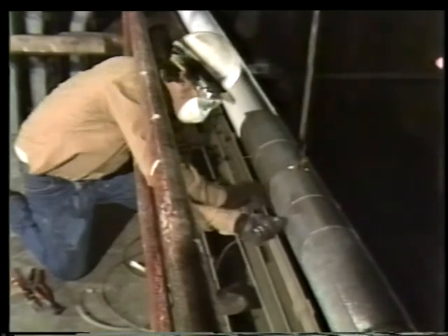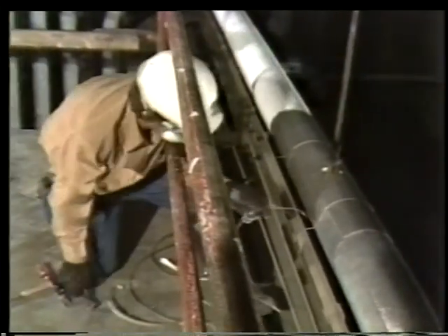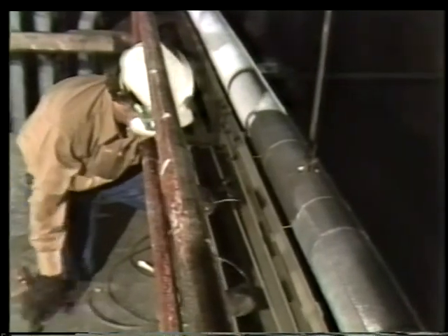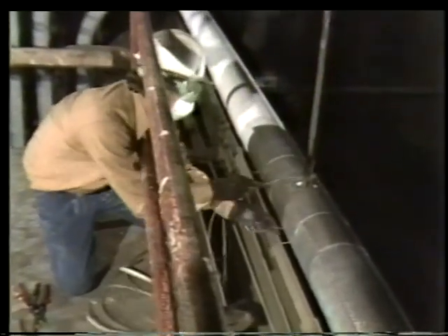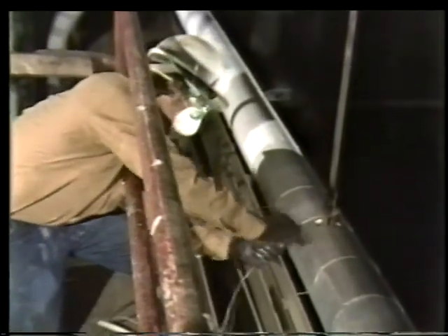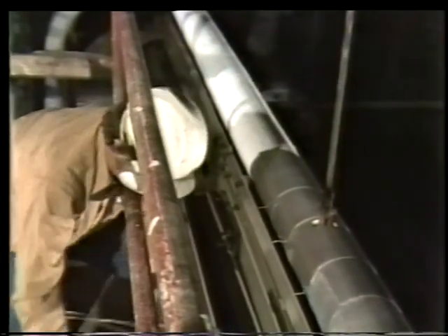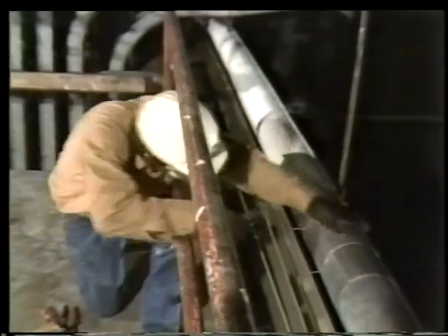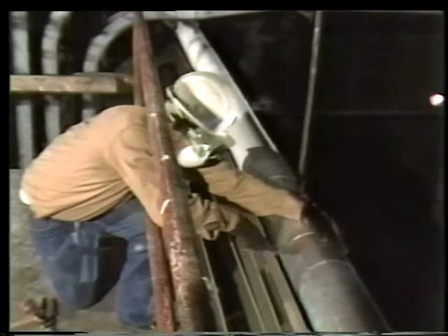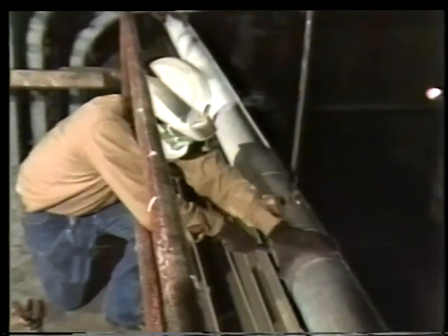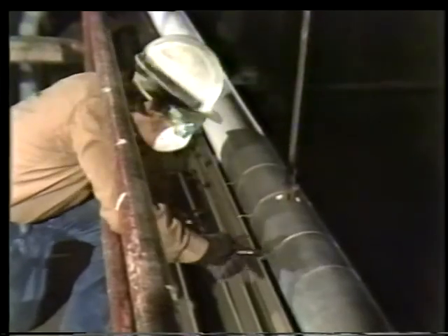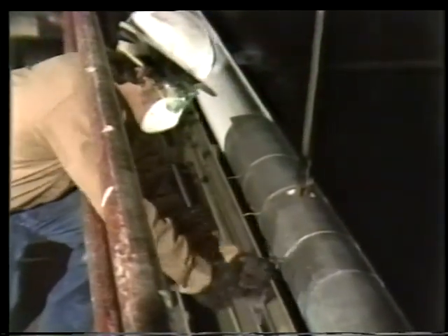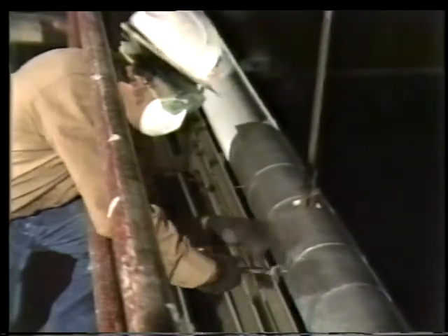Initially, the jacket is secured with wire ties. Wires are twisted on about 1 foot apart, just to hold the jacket tightly in place while it's banded. Even though they're only temporary, the wires are put on the jacket the same way they were installed on the insulation itself. At first, the wires are loosely twisted on, just to get their approximate position. Placement of the wires is not critical, but you have to think ahead. The bands go on next, so the mechanic makes sure to leave room for them by visualizing where they will go in advance. The bands will go between the wires, and then the wires will be snipped off.